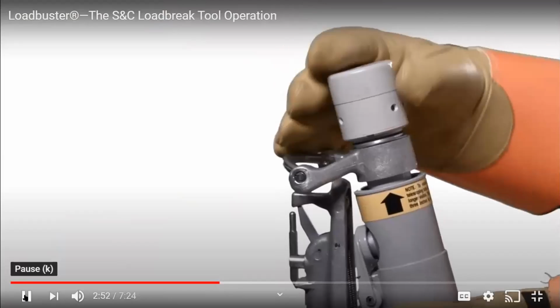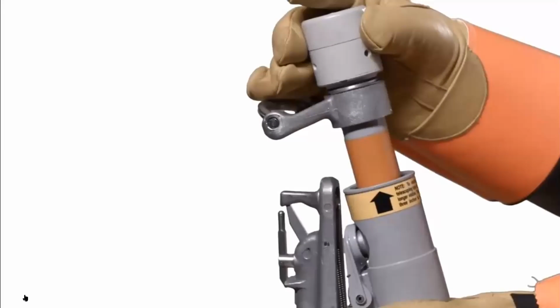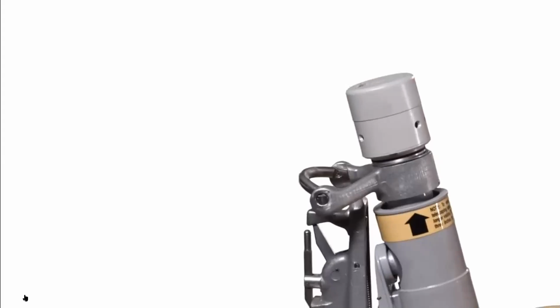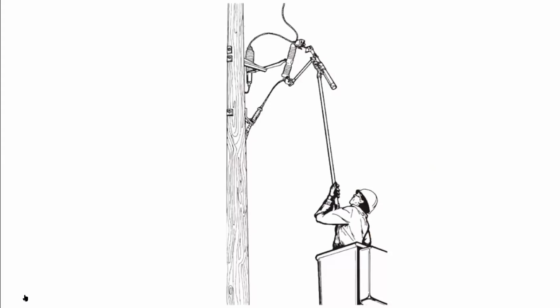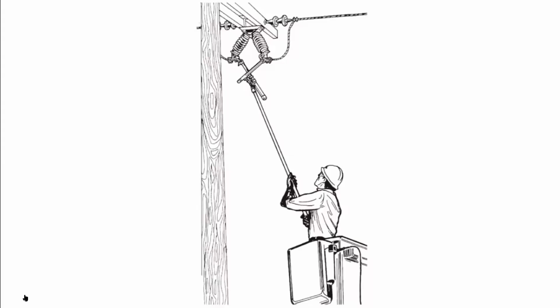Before operating, check for proper resetting of the load buster tool by extending the tool about 3 inches by hand. Throughout this travel, an increasing spring resistance should be felt. When operating from a bucket truck, stay at least 5 feet, 1.5 meters, below the device and in front of the fuse cutouts, fuse limiters, and vertically mounted disconnects and fuses. When disconnects are mounted inverted, approach the attachment hook from the hinge end, staying well below the device to be opened, so excessive horizontal force is not exerted on the insulator.